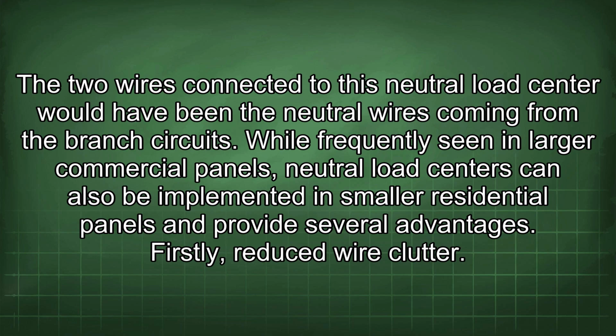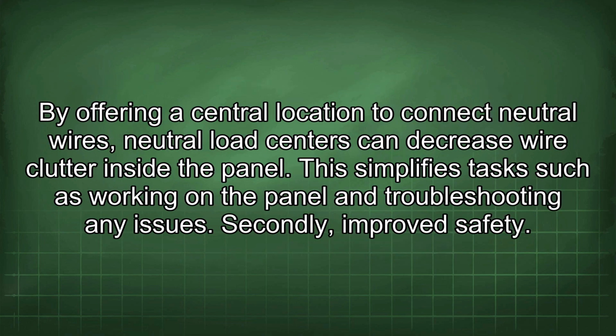While frequently seen in larger commercial panels, neutral load centers can also be implemented in smaller residential panels and provide several advantages. Firstly, reduced wire clutter. By offering a central location to connect neutral wires, neutral load centers can decrease wire clutter inside the panel. This simplifies tasks such as working on a panel and troubleshooting any issues.